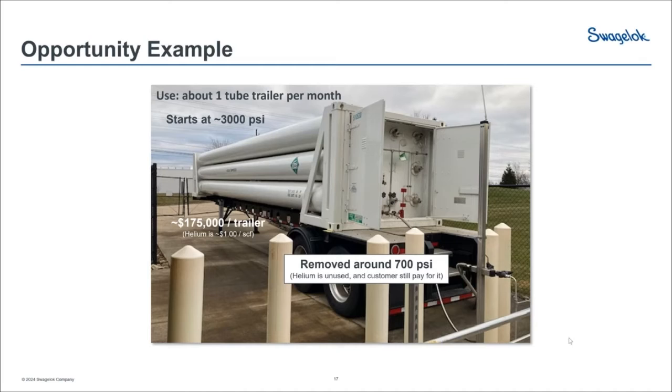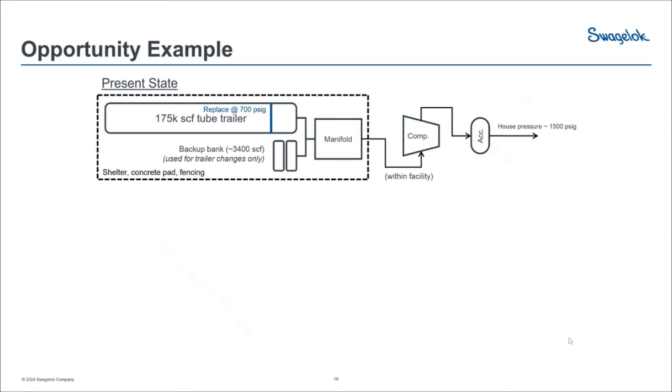You see, the customer had the best of intentions. 700 PSI equated to contingency operations for them of around 5 days. Now, 5 days also happened to coincide with the contractual leeway that the gas company was committed to delivering a new fresh trailer. So when we took stock of the customer's gas distribution system, we found something like this, a basic P&ID.